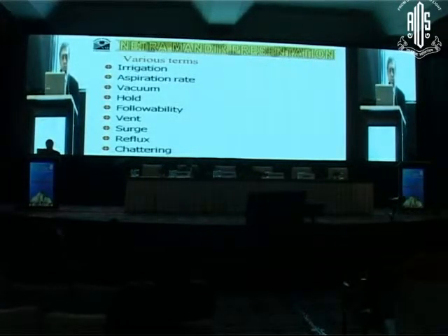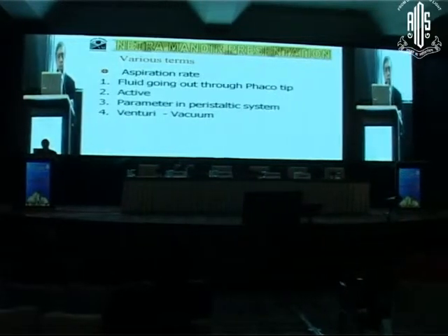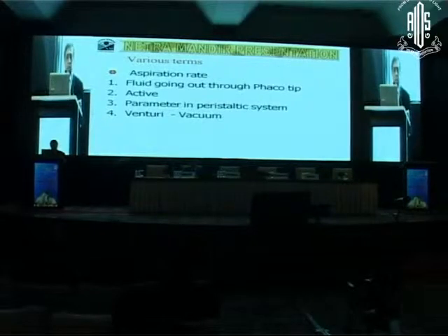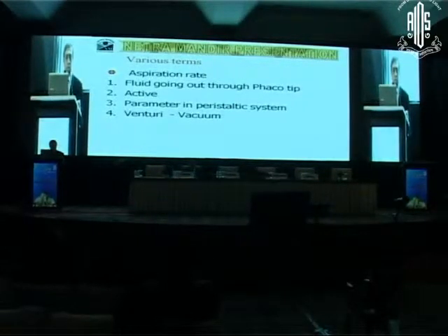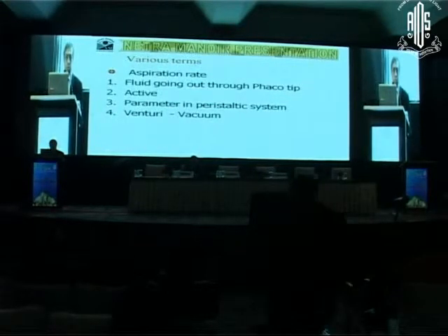These are various terminologies which we use during phacoemulsification, and let me start with each one of them. I am purposely taking aspiration as the first part, primarily because I believe that aspiration is an active process, because it is the machine which is functioning for the aspiration flow rate and takes away the fluid from the anterior chamber, by the rotation pump, into the back.